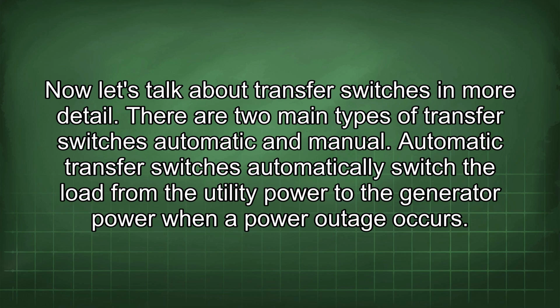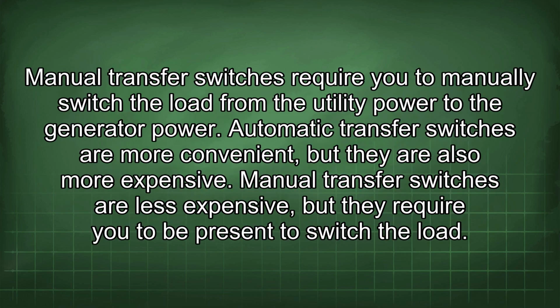Automatic transfer switches automatically switch the load from the utility power to the generator power when a power outage occurs. Manual transfer switches require you to manually switch the load from the utility power to the generator power. Automatic transfer switches are more convenient, but they are also more expensive. Manual transfer switches are less expensive, but they require you to be present to switch the load.